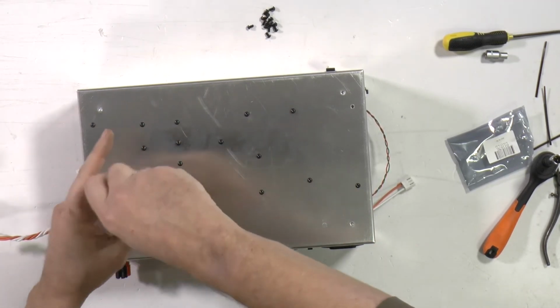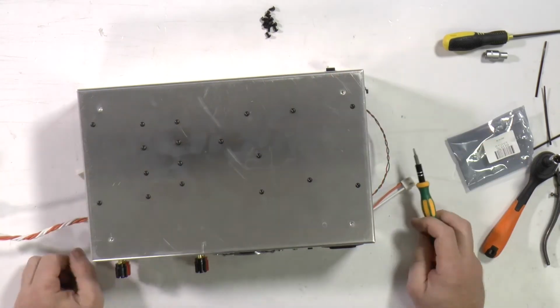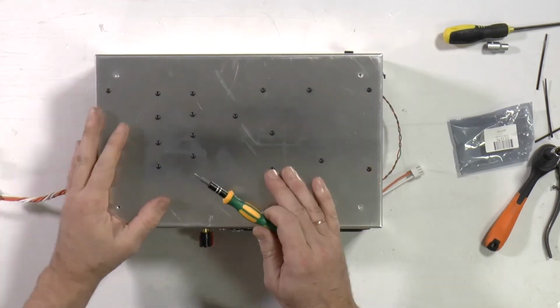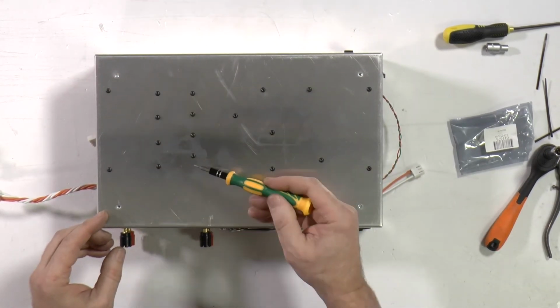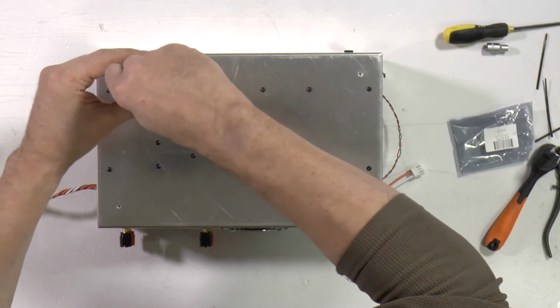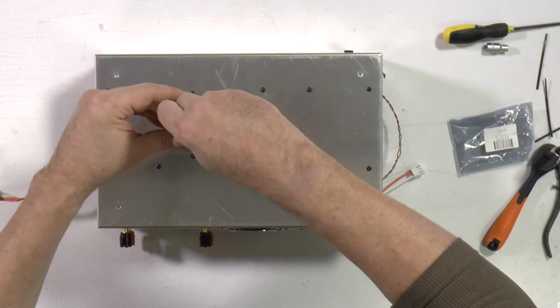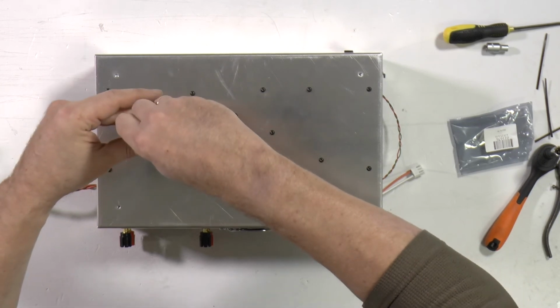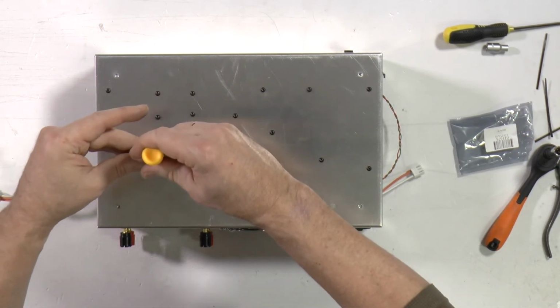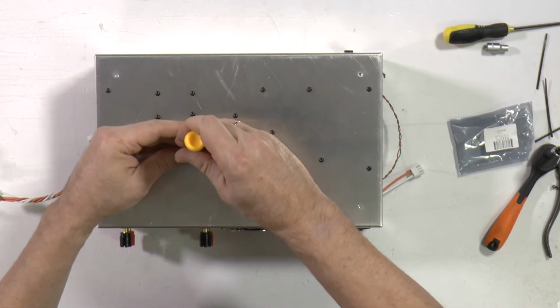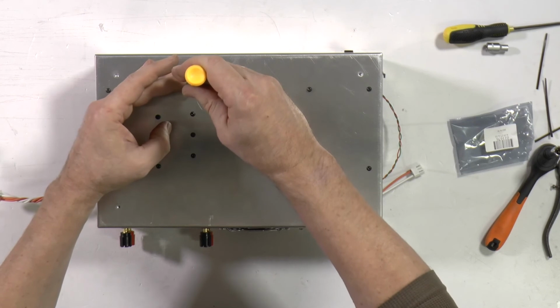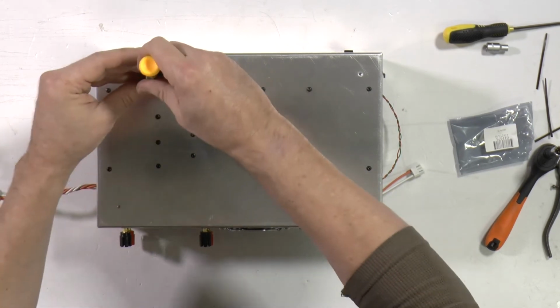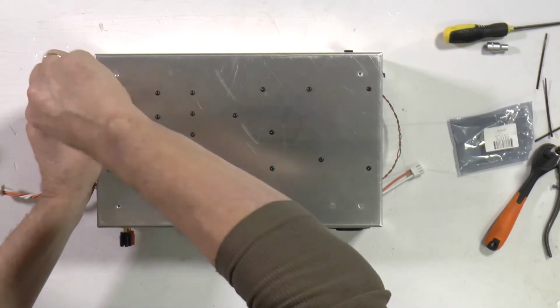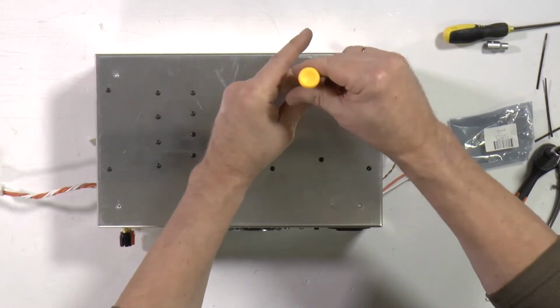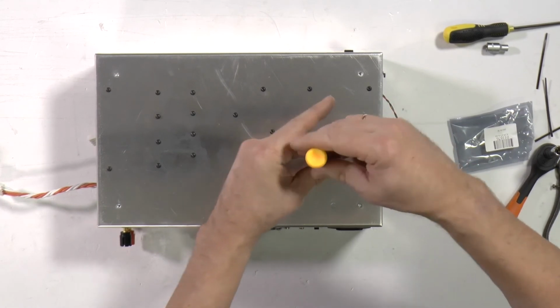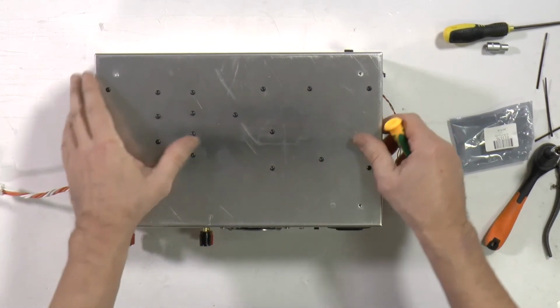Pay attention to the left side, there are 2 rows of screw holes. Start to tighten those 2 rows first. Below the surface there are 8 high temperature, high power MOSFETs, and you should provide a good connection with the chassis. These MOSFETs are set for very high temperature - the temperature protection triggers at 120 degrees Celsius. It's really high.